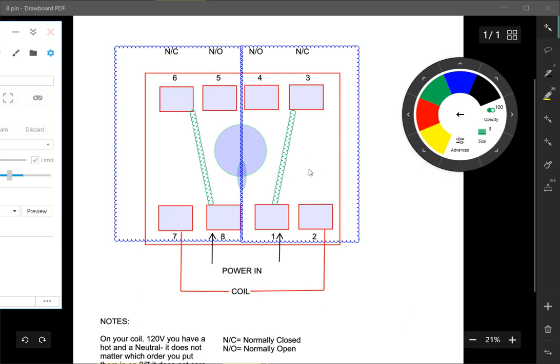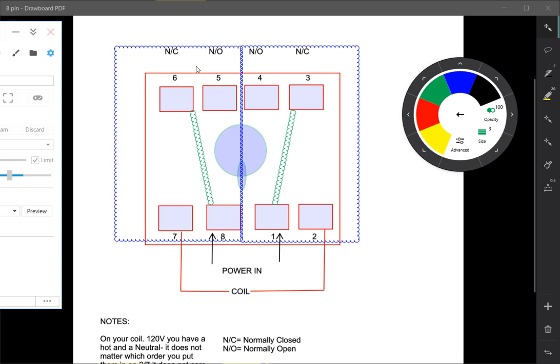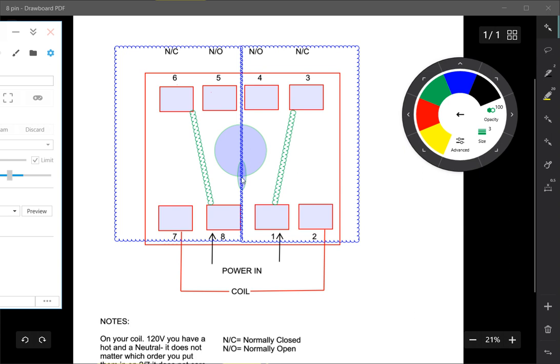The way that it is numbered is counterclockwise with the pin being down. So sometimes you'll run into an issue when you're troubleshooting when these numbers are faded and you're having a hard time remembering which is which. What you want to do is knowing that the pin is facing down, it goes counterclockwise from the pin. Starting counterclockwise on the first terminal, second, third, fourth, fifth, sixth, seventh, and eighth. So it goes in a counterclockwise motion around the pin when it's facing towards the bottom. That's the easy way to remember it.